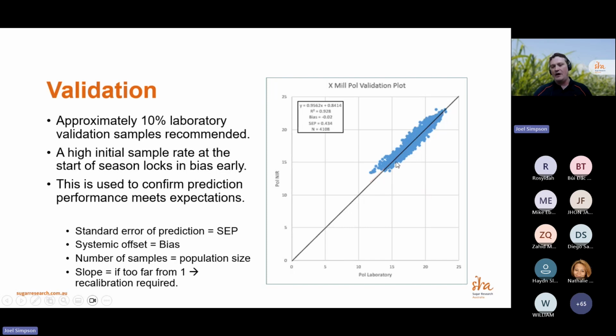The other factor is that if you have a small validation population, obviously what you can take from that information is not as much as if you had a bigger population. So that's another thing to consider. The other part of what you look at for validation is the width of that cloud. How broad is this cloud in relation to the error of the laboratory equivalent, just on the duplicate laboratory results? If it's all within limits, then we're good. If not, you might need to take some action.